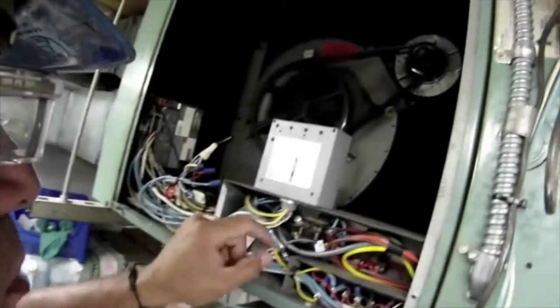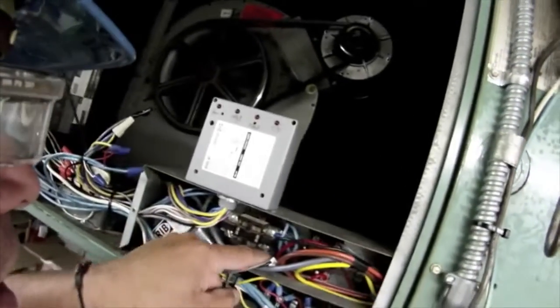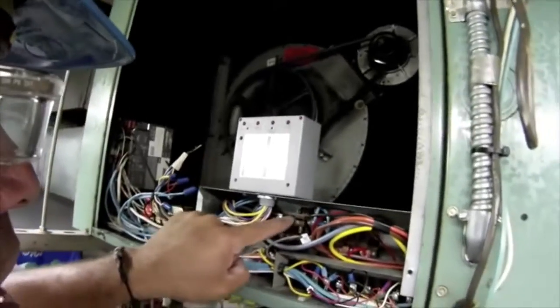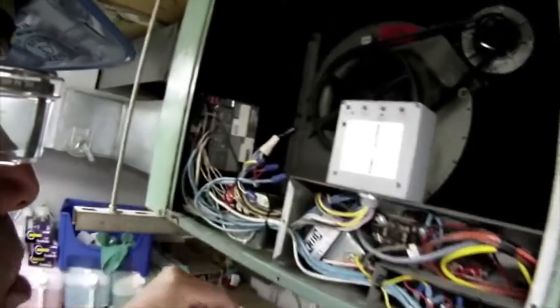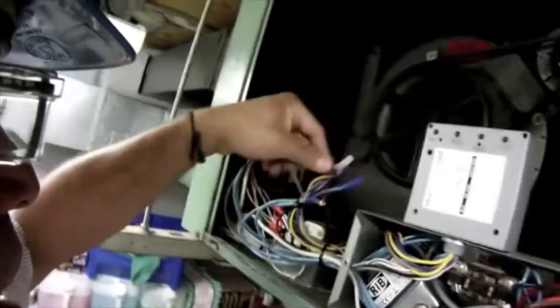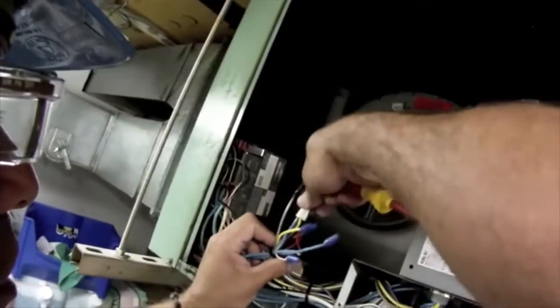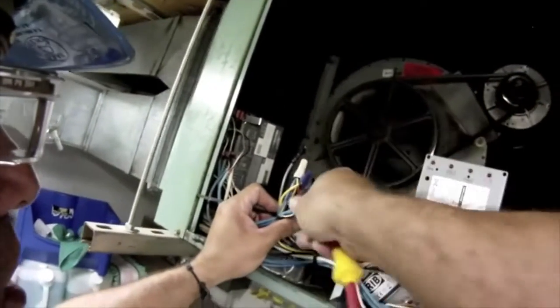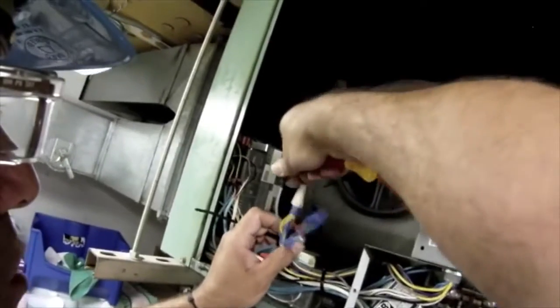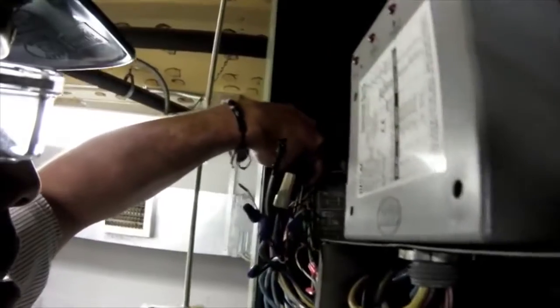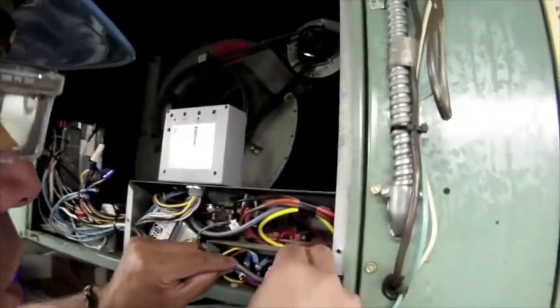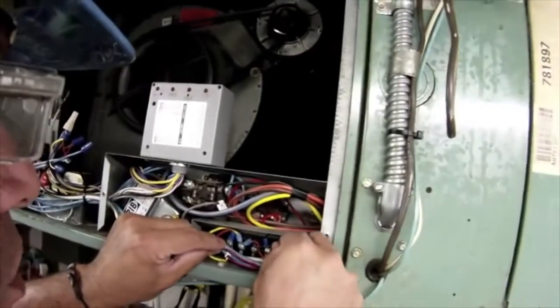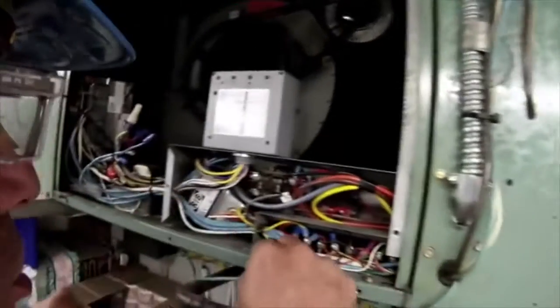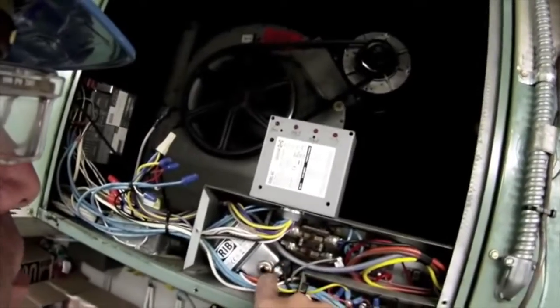As I'm looking at all my wiring connections, everything looks really good so far. The contactor is in good shape. None of the wires that I took apart and have put back together have fallen off. All my twist connectors are in good shape, and everything is nice and tight on the controller. That's where I did most of my activity. Also right in here, everything's still very nice and tight, nothing loose, nothing coming apart, and so I'm pretty happy with that.